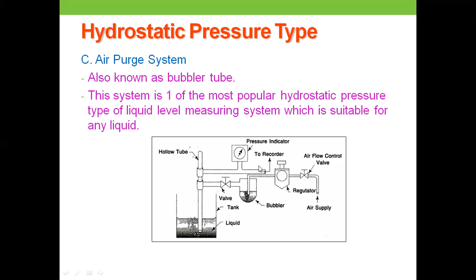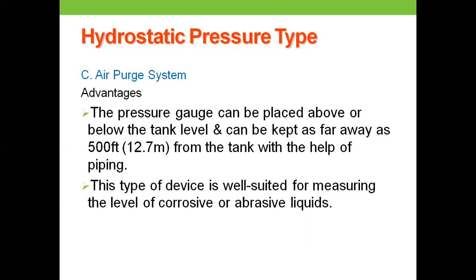Next, air purge systems advantages. It can be kept as far away as 500 feet. As we have seen here, this device is well suited for measuring the level of corrosive and abrasive liquids. So previously we discussed that for corrosive types of fluids, a sight glass system is not utilized at all.